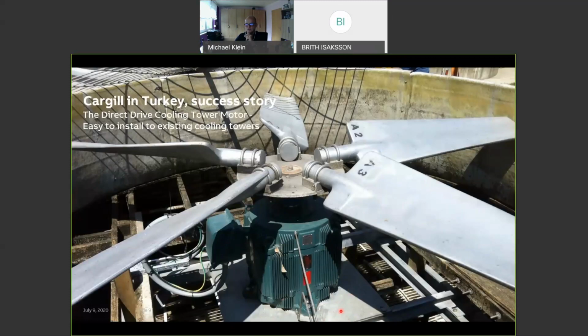Because the motor sits in the shadow of that plate and gets no airflow and no cooling air. So remember this when you see a cooling tower made out of wood, and think about or remember that picture here. And if you put an open grill in here where the motor sits on, which is as strong as this plate, and it's fine. Then the air can flow through this grill and then along the motor side and pick up the heat. Okay.